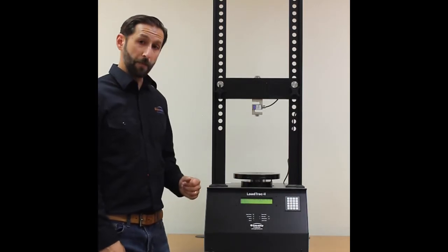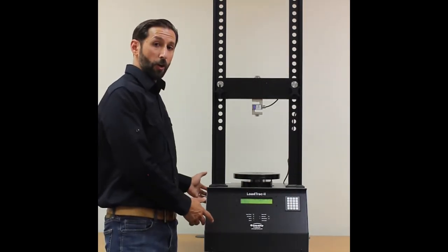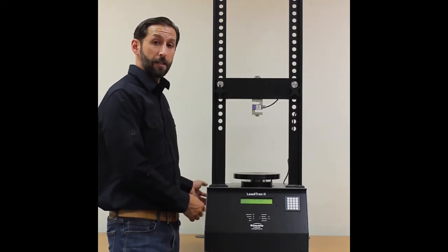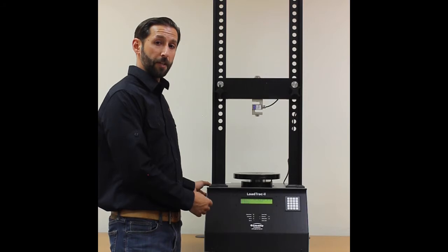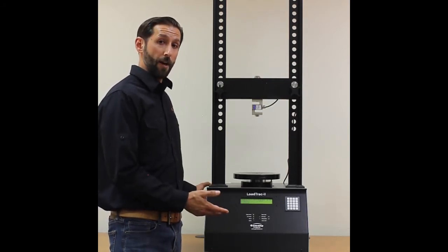Let's have a look around the system and see some of the components of the load frame. The lower unit here is all self-contained, houses the electronics and electromechanical motor assembly. No air compressor, hydraulics, or deadweights are required.